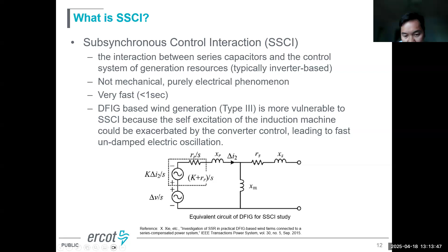This is the equivalent circuit of doubly-fed machines for SSR studies by Professor Xie from Tsinghua University, which explains SSCI pretty well. Basically, you have the rotor resistor, which is positive, but the slip is negative for the induction generator, which is why it's called the induction generation effect. Then you have the converter, which adds another factor K, making the induction generation effect more severe. So the induction generation effect could be exacerbated by the converter control — that's the reason behind this SSCI.